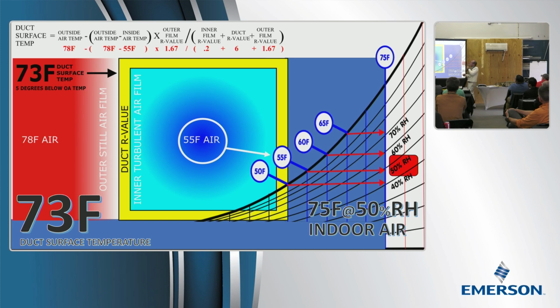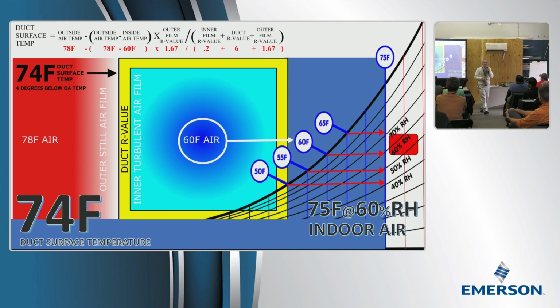This is why I like cold leaving air. What if we keep going? 60 degree leaving air. Not interested. That's why I like those 300 CFM per ton. I hear all the guys up north talking about crazy high CFM per ton. In my climate, it's all about the moisture. I don't care how long it runs. Let it run. I want it real slow across that coil because I know that if I get the air leaving at 60 degrees, it's going to be 60% relative humidity. Now that's before we start cooking noodles and taking showers. That's the result of operating the equipment. You're going to add to that with your infiltration, with your showers, with your noodles, with all that. So I like to start here. I like 50 degree leaving air.